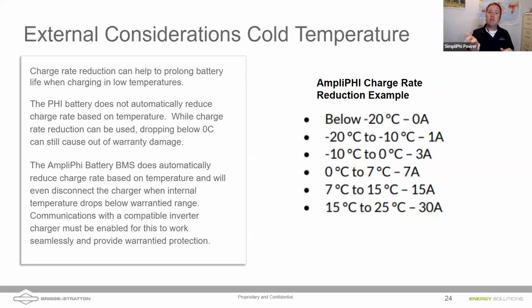Keep in mind that if you're using the Phi batteries, which are non-communicating, those don't have the ability to reduce the charge rate, so we'll want to make sure we utilize heating pads. But there may be a potential that if you're in a cold climate and leveraging the AmpliPHI or SimpliPHI batteries, which can tell a piece of equipment to reduce its charge rate, we may be able to get away without having heating pads.